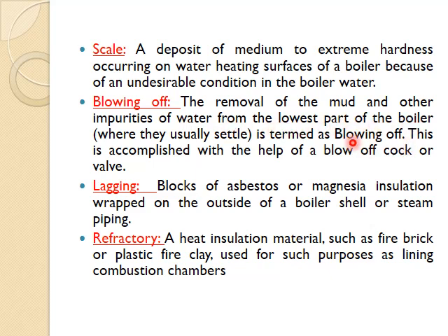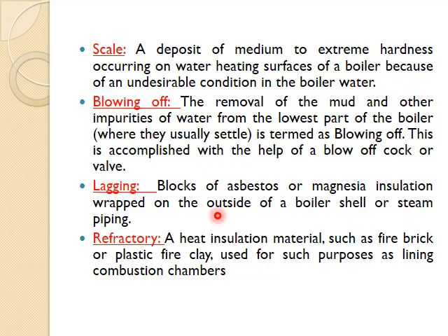Blowing off: the removal of mud and other impurities of water from the lowest part of the boiler — where they usually settle — is termed as blowing off. This is accomplished with the help of a blow-off cock or valve.